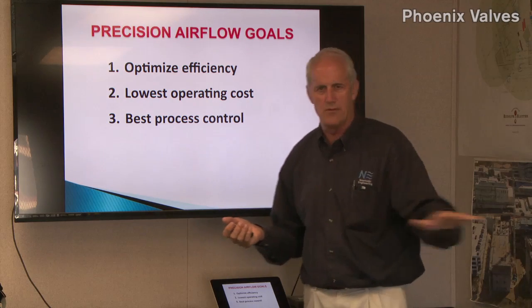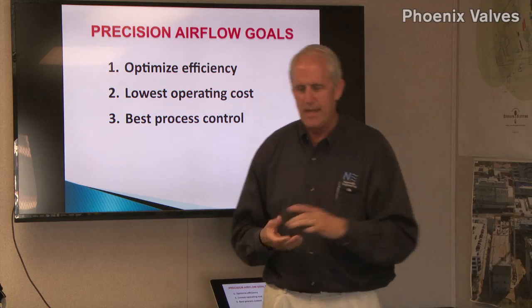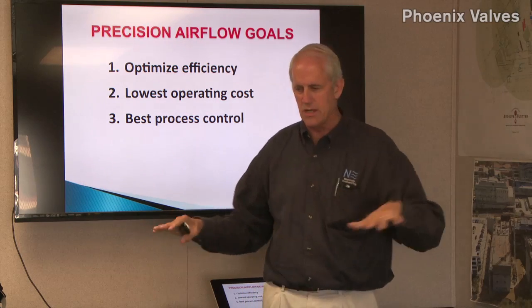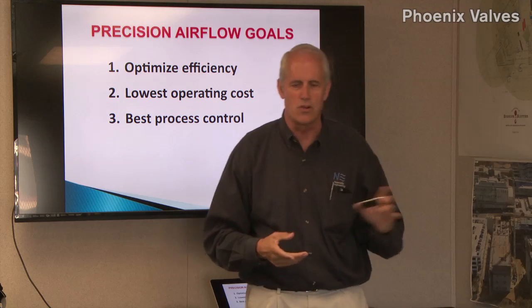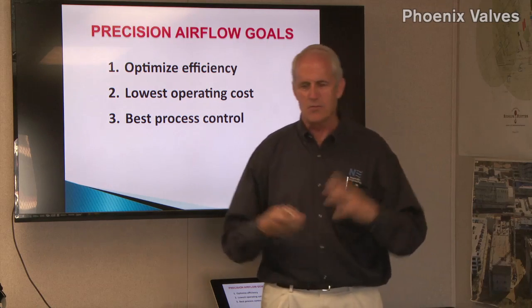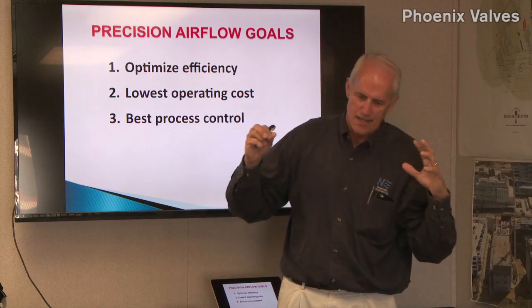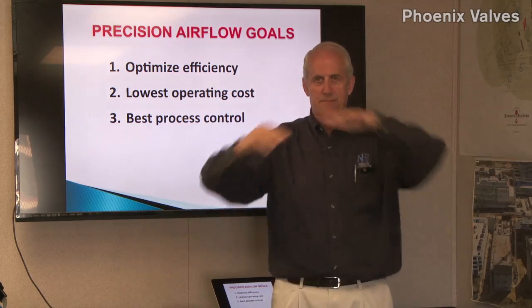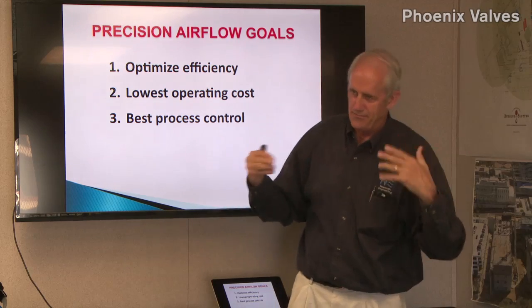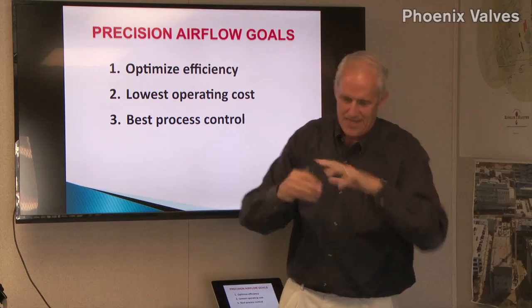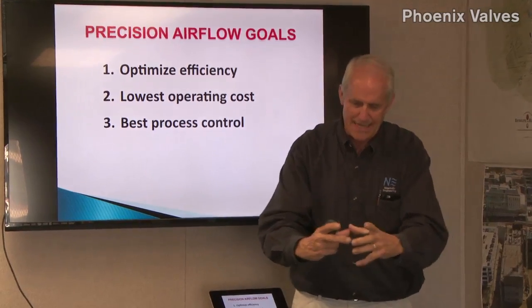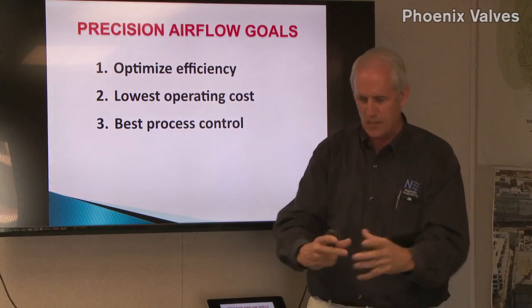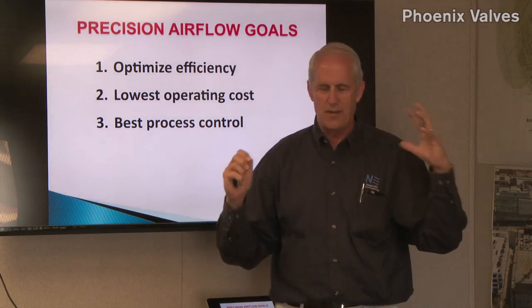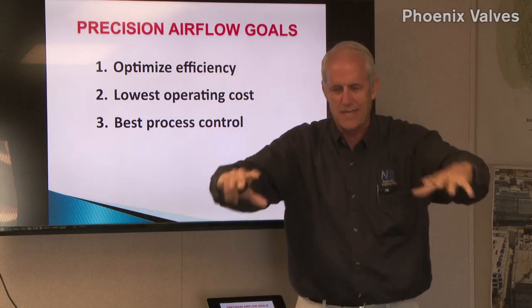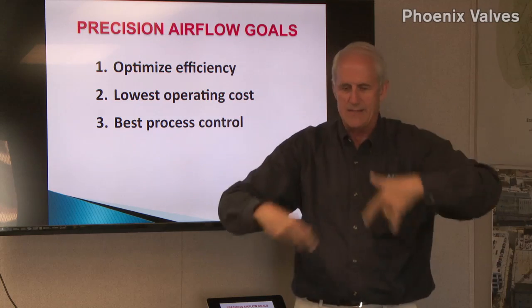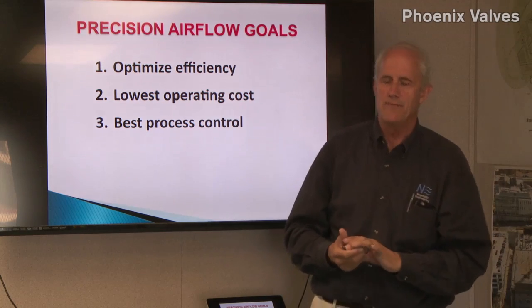I'm talking about now lower level 3 west, so in the vivarium level, that's what we're talking about. You've got to have excellent process control at all times, and you can't be uncomfortable. Even if you look at the way a vivarium room is designed, the holding rooms, the room itself, they call the macro environment when you get into veterinary stuff a lot. The macro environment, and then they put them in these little cages, micro-isolator cages, and that's called the micro environment. So the principle is you deliver air comfortably into the macro environment, and then there's fans on top of the cages that deliver it into the micro environment.